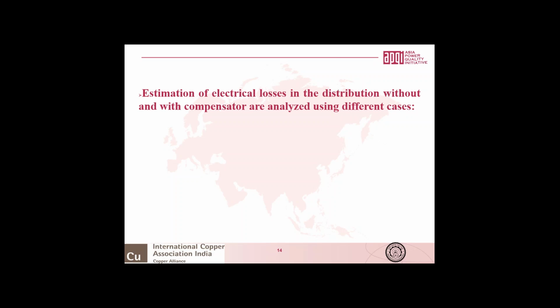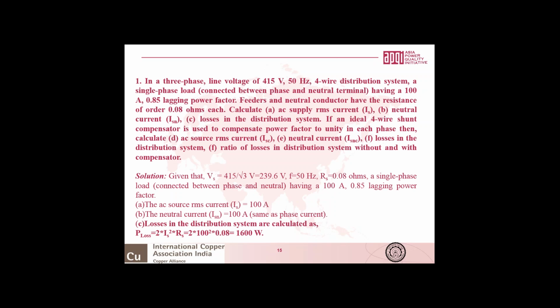So going to typically a first example, and it's an interesting example only of linear load. So we are taking an example in a 3-phase, 4-wire distribution system with a line voltage of 415 volts at 50 hertz. Typically, let's say we have a single phase load which is connected between phase and neutral and having a current of 100 ampere with a 0.85 lagging power factor. Considering that the feeder and neutral conductor have a resistance of typically 0.08 ohms each.